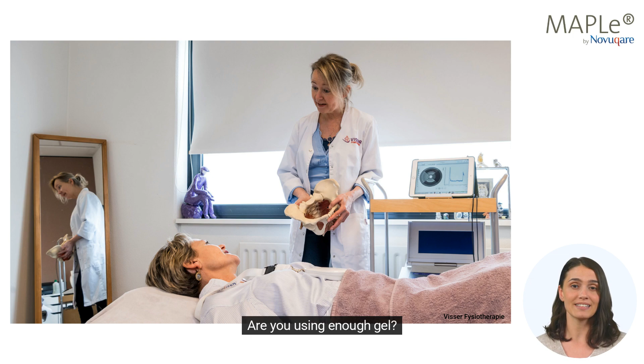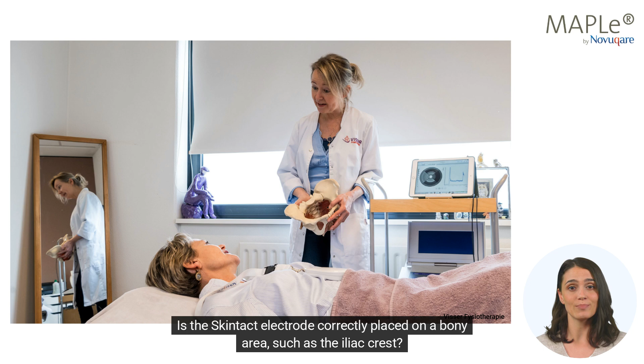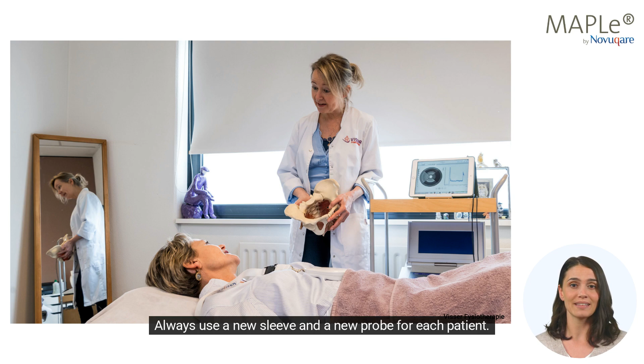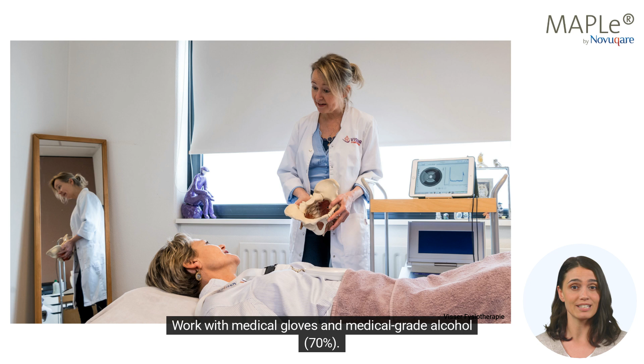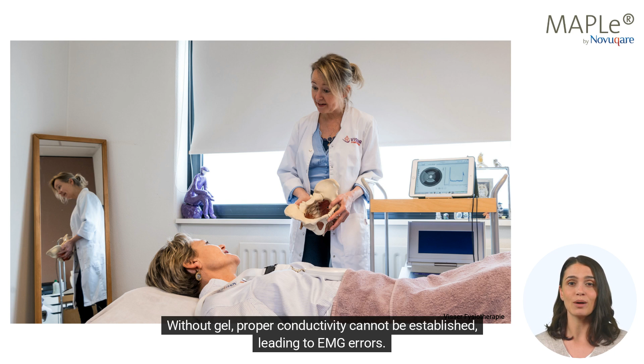One. Check your equipment. Is the probe properly connected? Are you using enough gel? Is the Skintact electrode correctly placed on a bony area such as the iliac crest? Always use a new sleeve and a new probe for each patient. Work with medical gloves and medical-grade alcohol, 70%. Applying gel. Apply sufficient gel to the electrode. Without gel, proper conductivity cannot be established, leading to EMG errors.